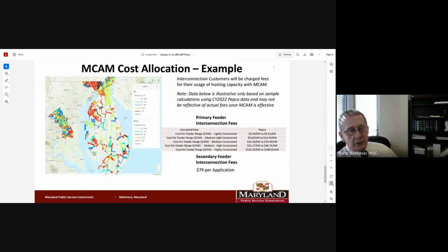Back in phase 2 of the work group's efforts, our mission was to eliminate obstacles to interconnection. We had situations where utilities had to close their circuits to interconnections because there was no more available hosting capacity. This is at the primary level, but it could also affect a residential homeowner. We're not talking about a service transformer, we're talking about a feeder limit where there's no hosting capacity available, so you have to restrict interconnections.